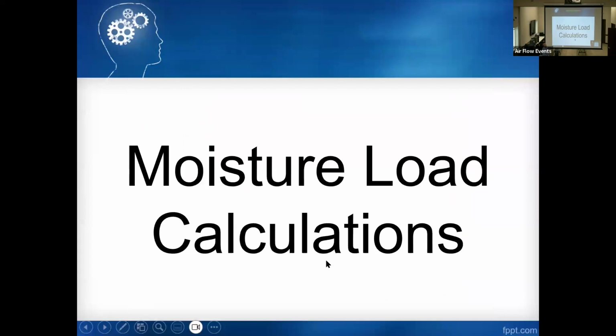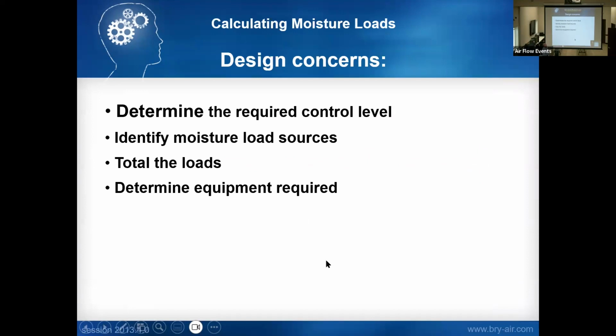So one of the critical things with sizing humidifiers is doing the moisture calculation. So we'll spend a few minutes going over some moisture calculations. Basically, one, you want to identify the required level. Do you need to maintain a space for 45%, 10% RH? What's your space control point, same with temperature. You want to identify your sources of load for the moisture. We'll go over a lot of the common load sources here in a few minutes. You want to add your total load and then determine the equipment required.